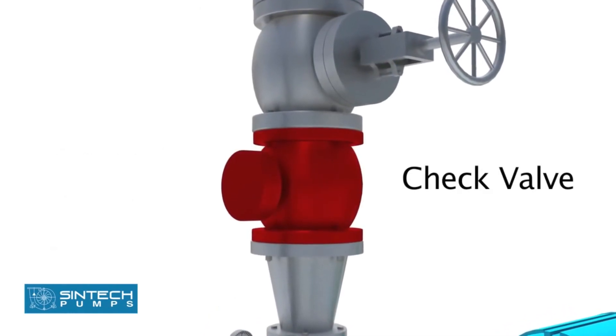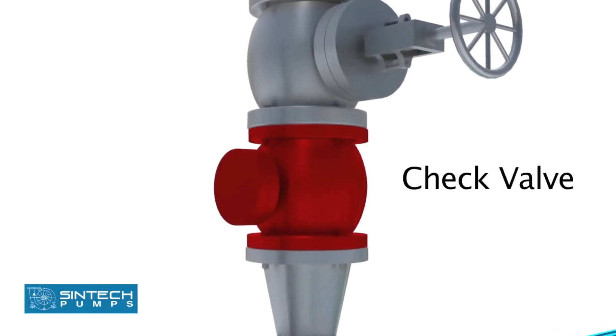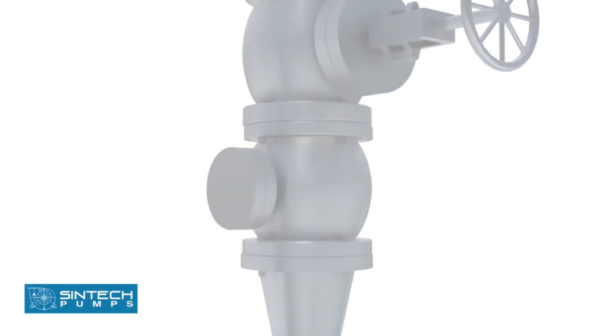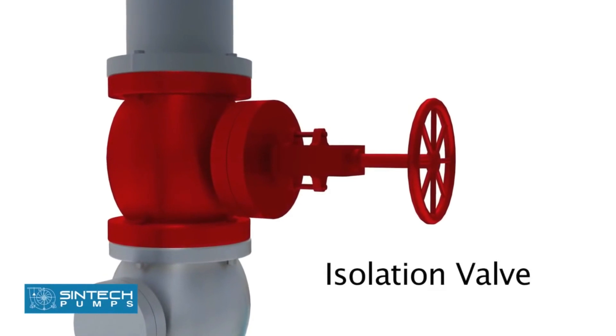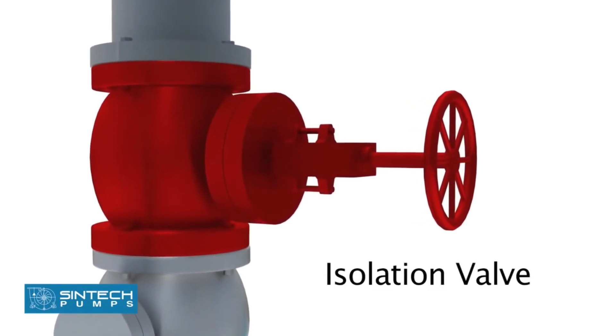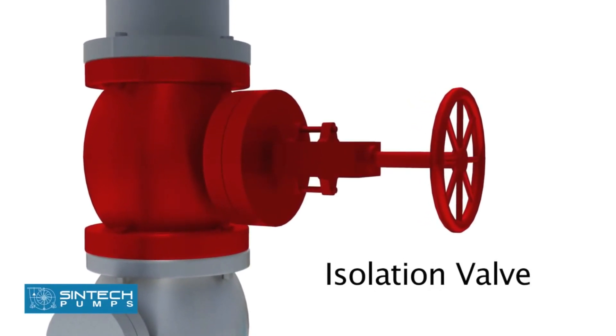The check valve used in the discharge should be of non-slam type to prevent hydraulic shocks. The isolation valve is provided downstream of the check valve so that these can be taken up for servicing whenever required.